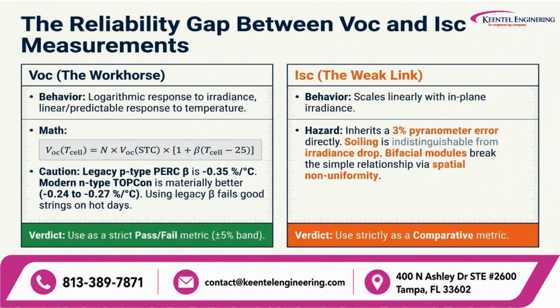Not all DC field measurements carry equal analytical weight. Open circuit voltage, or VOC, is our reliable workhorse. It responds logarithmically to irradiance and linearly to temperature. Note that with the industry transitioning from P-type PERC to N-type TOPCon modules, temperature coefficients improve from minus 0.35% down to minus 0.24% per degree Celsius. Failing to update this coefficient will falsely fail good strings in high heat environments. Conversely, short-circuit current, or ISC, is inherently volatile. It inherits pyranometer sensor error directly and is heavily distorted by bifacial albedo variations, making it suitable only as a comparative metric rather than an absolute pass-fail gate.